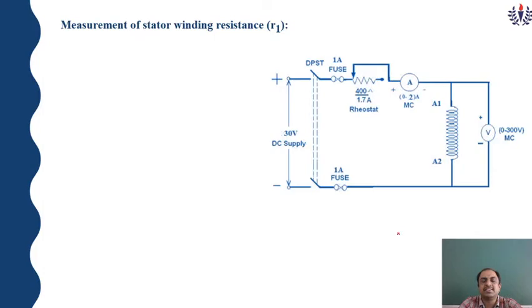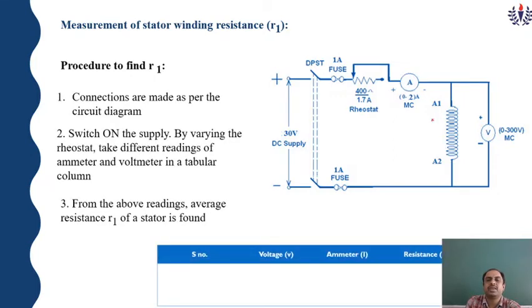Measurement of stator winding resistance. I am taking a DC supply, which is given through a double pole single throw switch, that is DPST. A 1 ampere fuse is needed. It is given to a rheostat and connected to the ammeter, voltmeter and winding arrangement. If you vary the rheostat when you give the supply, you can measure the voltage and current, and then calculate R. We know Ohm's law, V equal to I into R, therefore R equal to V by I. By using this we can measure the resistance.